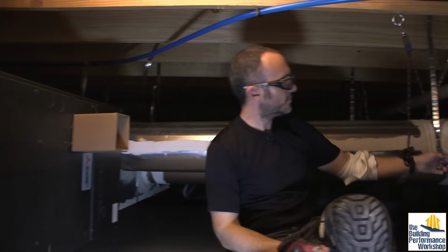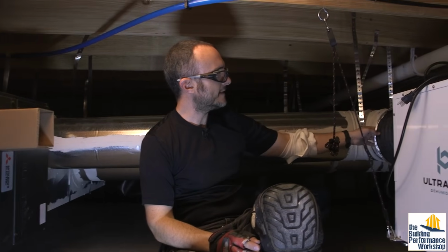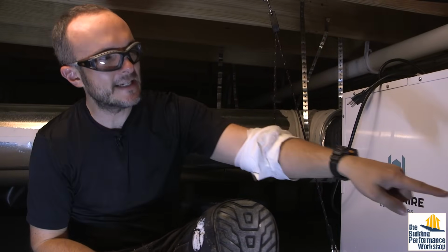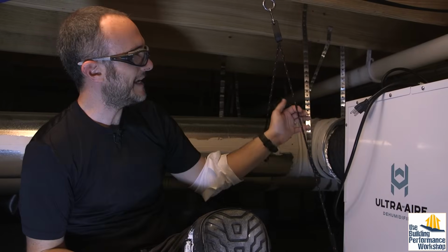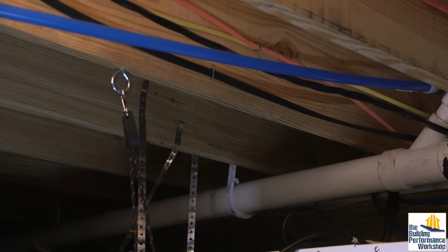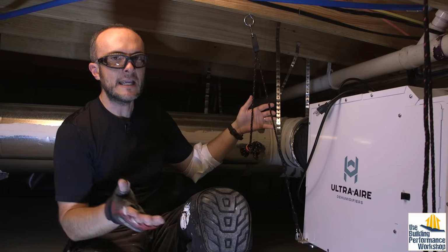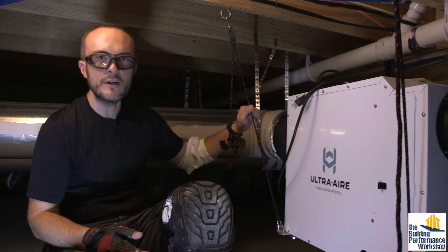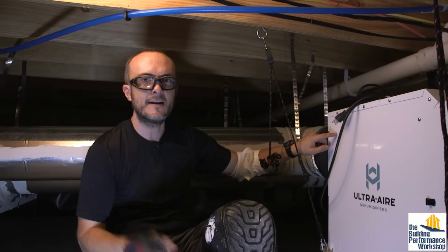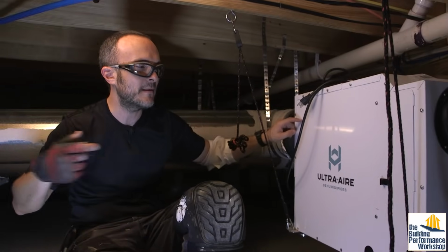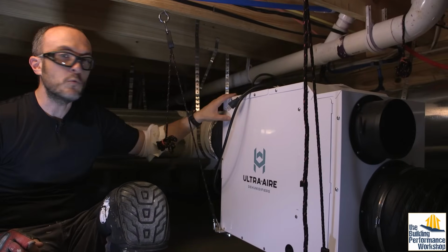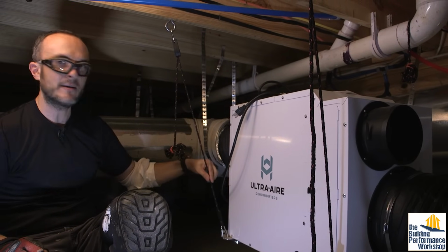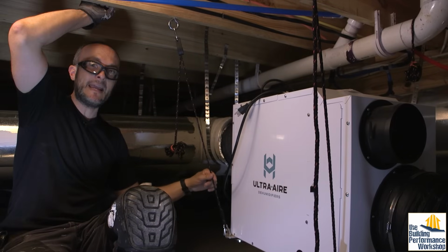By the way, one thing I wanted to point out: here you can see that's the sound of our other dehumidifier kicking on. We've got flex duct on both sides of this, and we've got this cool little hang kit. This hang kit is from Ultra-Aire, which is owned by Santa Fe, so you can get it for either Santa Fe or Ultra-Aire systems. But it's nice that it's not rigid. So when this piece of equipment does kick on, like what you just heard upstairs, maybe you can't hear that, maybe I'm just super sensitive to it, it will hum a little bit because it's got a compressor built into it. And so this decouples that vibration from the structure of the house, which I'm hanging it from.